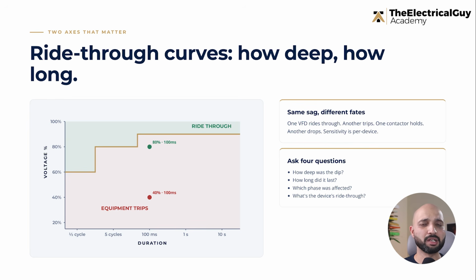One VFD may ride through, another VFD may trip. One contactor may hold, another may drop. One PLC may continue, another may reset. So when engineers investigate a voltage sag problem, they should not only ask what the supply voltage was, they should also ask what the minimum voltage was, how long it lasted, which phases were affected, which equipment tripped, and what the ride-through capability of that equipment is. So there is no single solution that works for every site. The correct solution depends on the process, equipment sensitivity, cost of downtime, fault history, utility system, and budget.